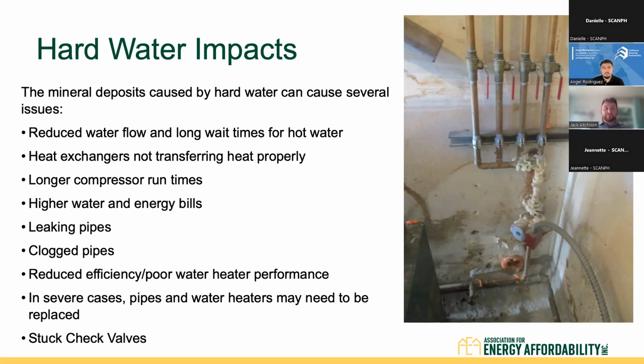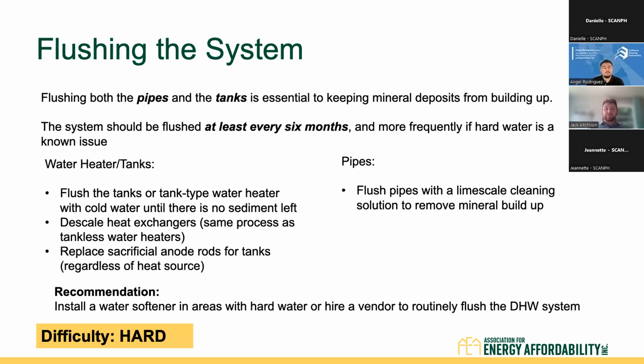Next slide, please. So, flushing the system. Flushing both the pipes and tanks is essential to keeping mineral deposits from building up. The system should be flushed at least every 6 months, and more frequently if hard water is a known issue. Water heaters and tanks: flush the tanks or tank-type water heater with cold water until there is no sediment left. Descale heat exchangers, same process as tankless water heaters, and then replace sacrificial anode rods for tanks regardless of heat source. And for the pipes, flush pipes with lime scale cleaning solution to remove mineral buildup.